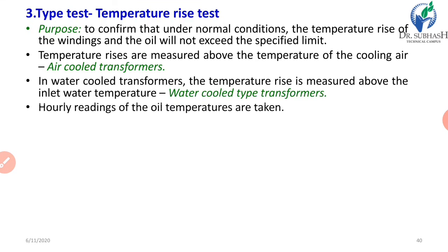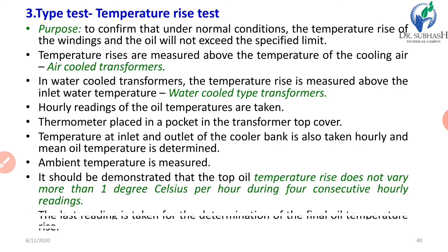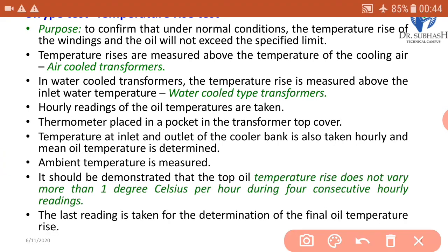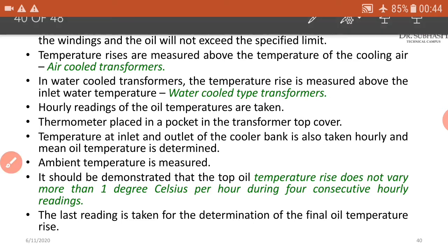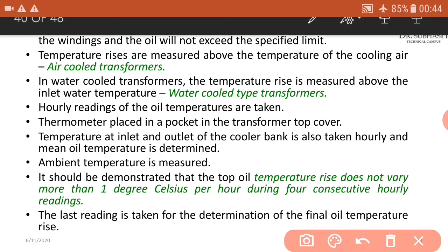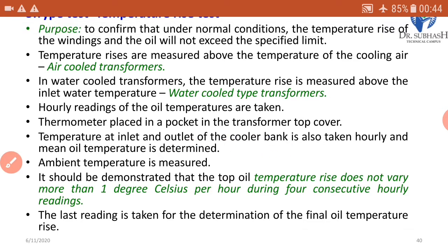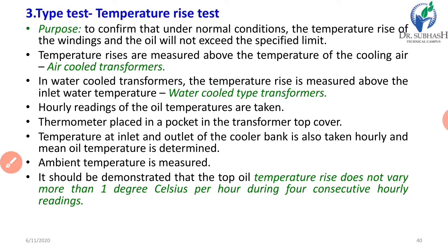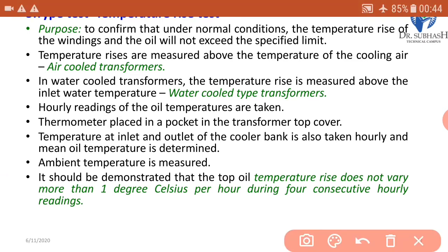Now type test. Temperature rise test. And what is the purpose? To confirm that under normal conditions the temperature rise of the winding and the oil will not exceed the specified limit. Temperature rises are measured above the temperature of the cooling air.